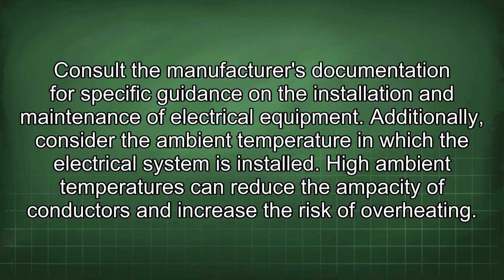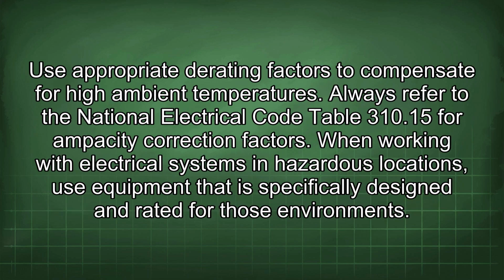High ambient temperatures can reduce the ampacity of conductors and increase the risk of overheating. Use appropriate derating factors to compensate for high ambient temperatures. Always refer to the National Electrical Code Table 310.15 for ampacity correction factors.